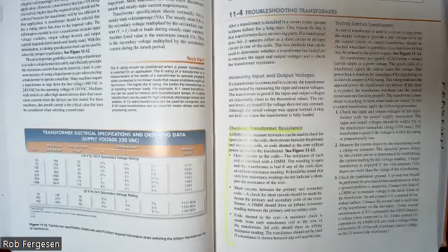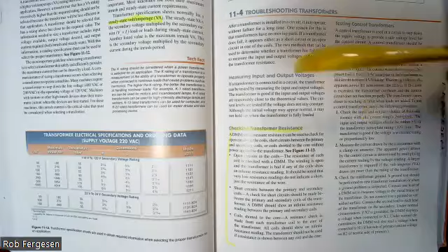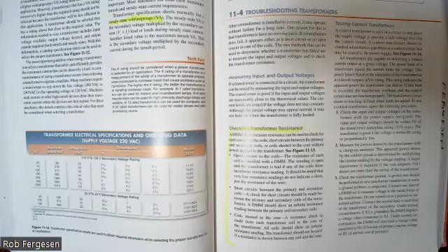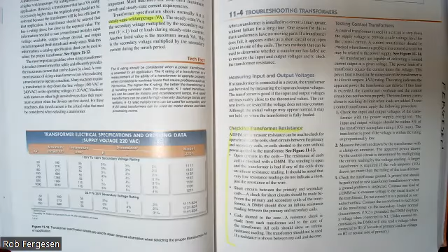They're not sizing the transformer based on a brief input load. You always want to set it up based on steady state voltamps. And every transformer is going to be a little bit different. You always need to check your transformer specifications to be sure you understand what its ability is to handle loads. Also recognize that if your transformer is in a hotter environment, then you probably need to upsize it and you need to look at the specs of transformers.